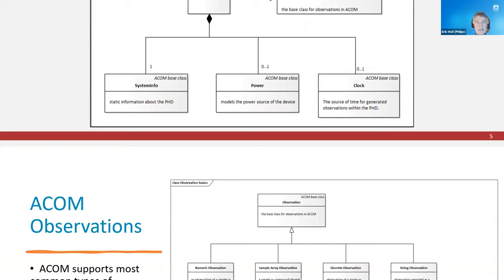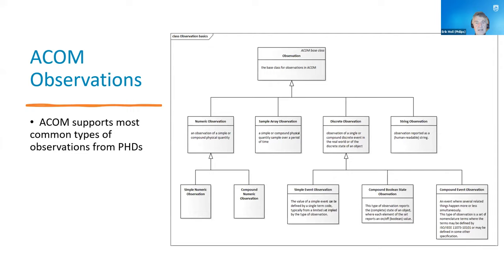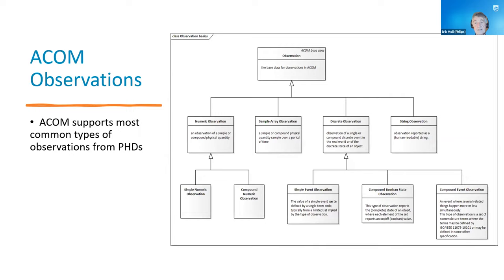Zooming into the observations, there's one base class. From the base class, we derived the main categories that personal health devices generate. There are numeric observations in single and compound form. There's a sample array that can be used for waveforms. There are discrete observations that report events or state values. And if that's not enough, you can also use a string observation, though we try to avoid that in the IEEE personal health domain context.